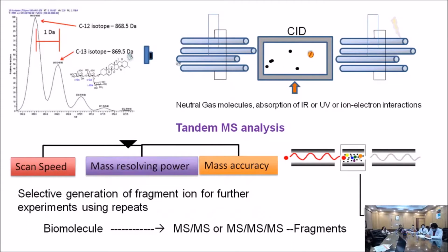These kinds of mass spectrometers work at unit mass resolution, compared to HRMS, which I discussed in the previous proteomics seminar, that has very high resolution—more than 1 lakh. Here, this triple quadrupole analyzer works with unit mass resolution, but what you get is the highest sensitivity, to the extent of femtomoles.